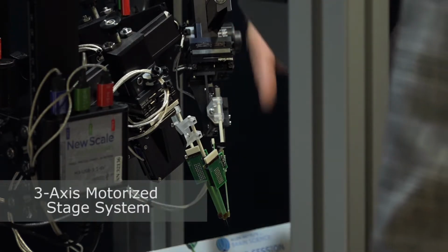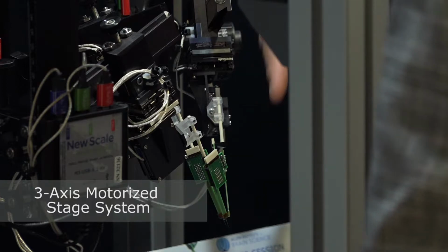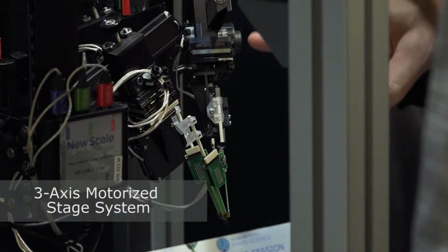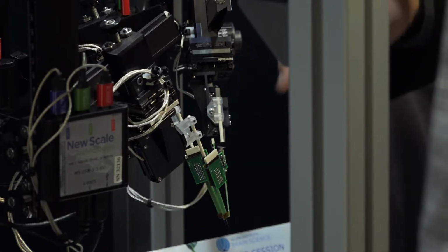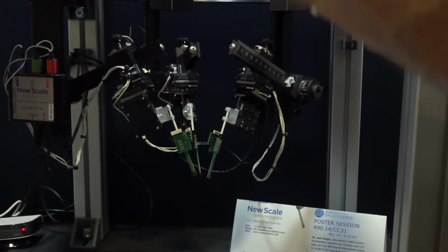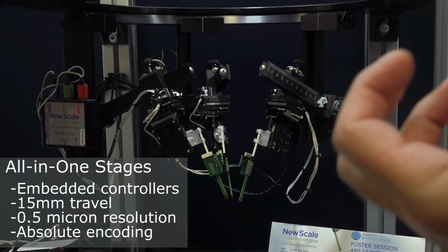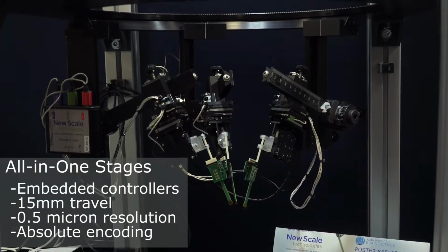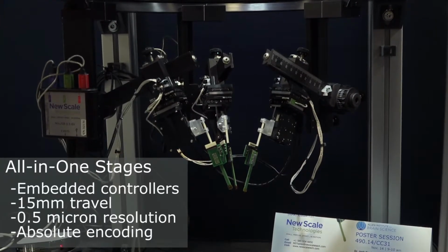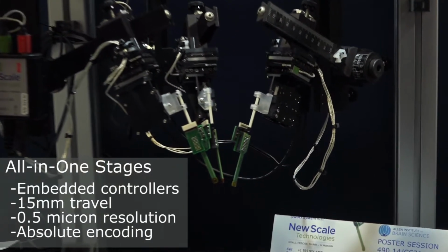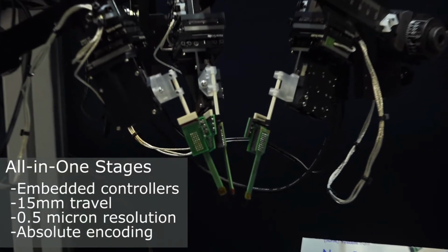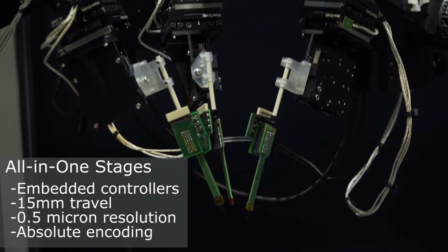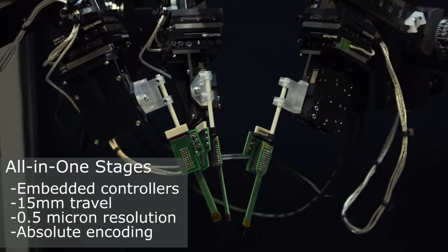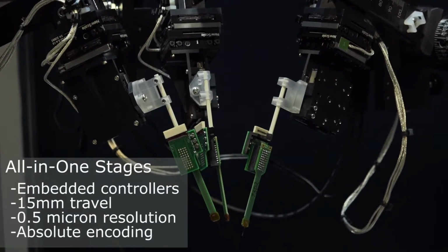You can see there's an axis along the approach, parallel to the probe. Then there's 2 axes that are orthogonal to the probe. These stages are all-in-one stages, so they have embedded inside position feedback and the driving control electronics. For each stage, there's 15 millimeters of travel and 0.5 micron resolution. So you can command any sequence of movements that you like with 0.5 micron resolution.